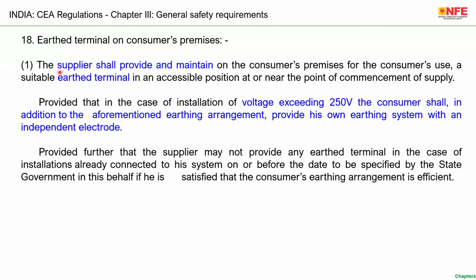Sub-regulation number 1: The supplier shall provide and maintain on consumer's premise for the consumer's use a suitable earthed terminal in an accessible position at or near the point of commencement of supply. So the sub-regulation is crystal clear. The supplier shall provide and maintain on consumer's premise for the consumer's use a suitable earthed terminal. So it is the responsibility of the supplier to provide an earthed terminal.